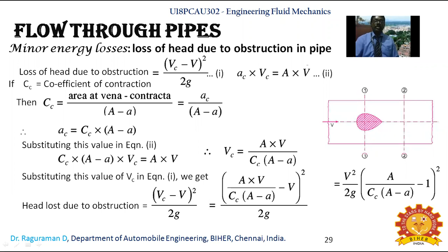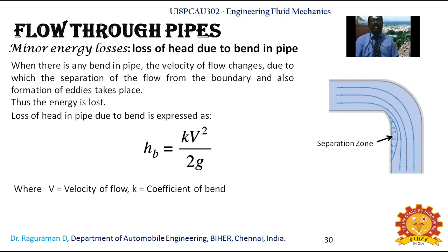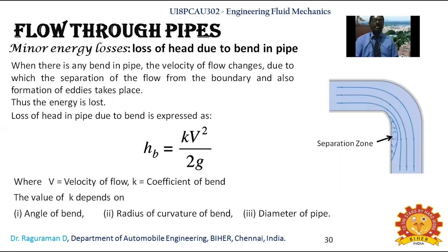Now about head loss due to bending. Whenever there is a bend in a pipe, that also results in minor losses. That loss we consider as K V square by 2G, as we had seen earlier. Similar to that, we get the losses in the case of a bending pipe. The K value depends on the angle of bend, the radius of curvature of the bend, and the diameter of the pipe.